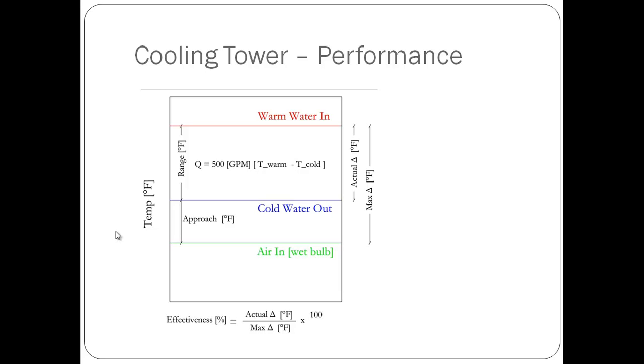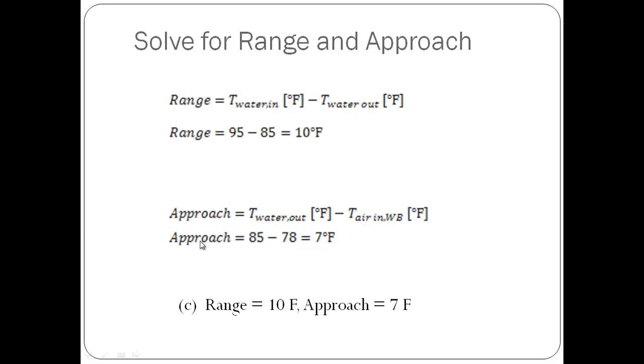So let's solve our problem by plugging the values into the equations. For range, we get 95 minus 85 equals 10 degrees Fahrenheit. For approach, we get 85 minus 78 as the wet bulb...